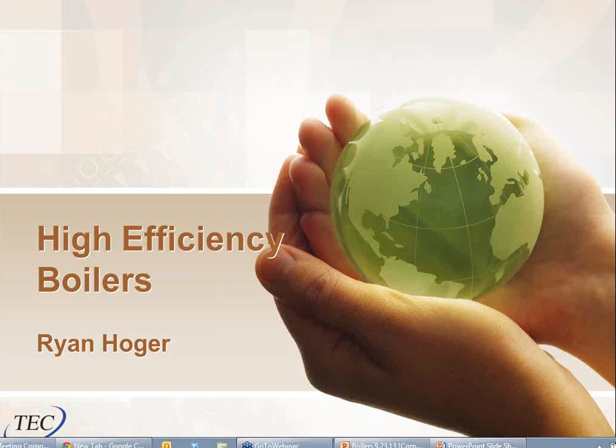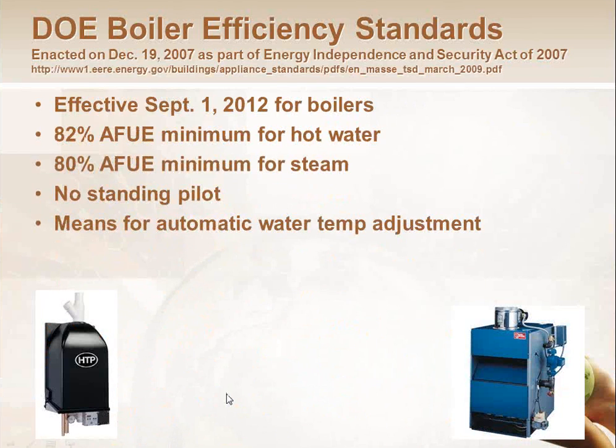All right, so high efficiency boilers. First thing to know is that on smaller boilers under 300 MBH, the federal laws changed from the Department of Energy last year, and the new legal minimum for those size boilers, for all boilers, condensing or non-condensing, is 82% AFUE. You can't have anything less efficient than that. If you have something older in your inventory, you can sell it and install it, but they cannot manufacture anything lower than that anymore. As part of that exact same ruling, standing pilots were eliminated completely, so everything has to be some sort of electronic-based ignition, no burning gas when you don't need it.